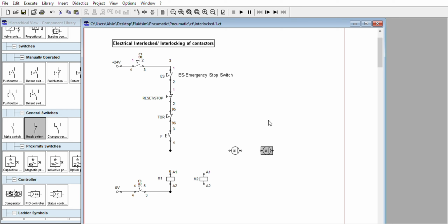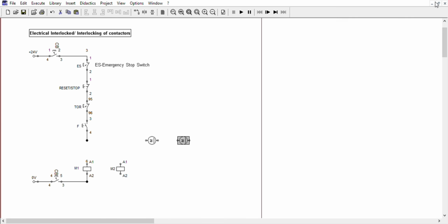Even if you press motor number 2's push button, you cannot start it because there is an electrical interlock. The contact is preventing motor number 2 from functioning, or either way. If this one is started first, you cannot start motor number 1 unless you de-energize motor number 2 first. So we'll add the components we'll supply. We'll name them motor number 1 and motor number 2.